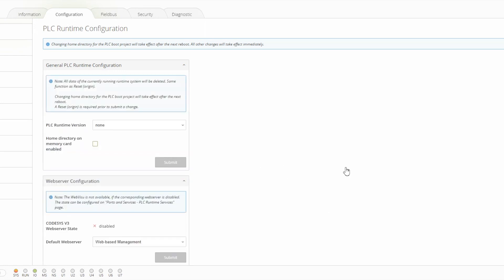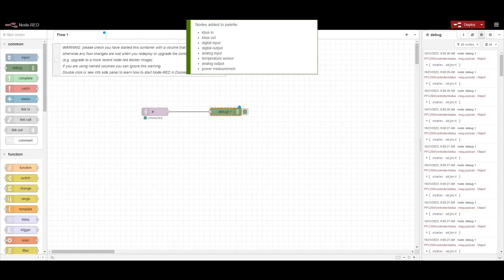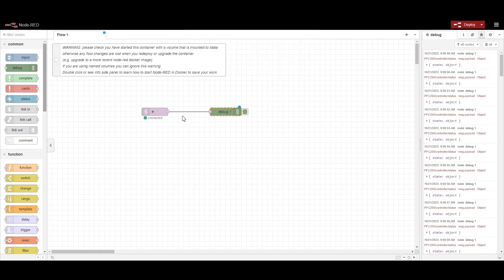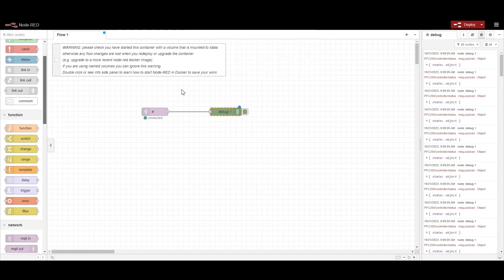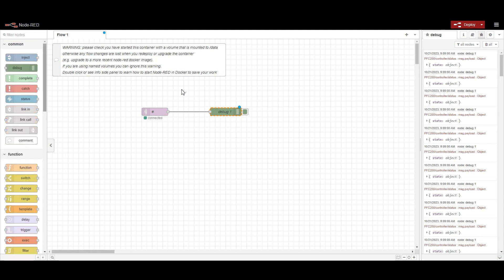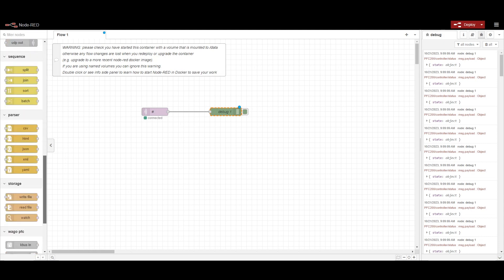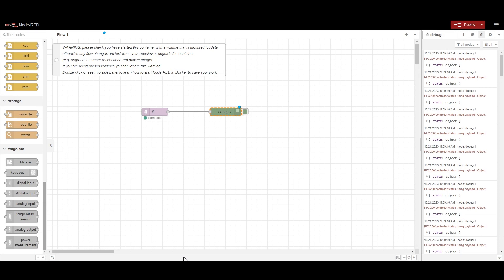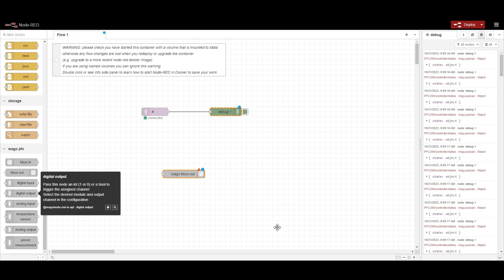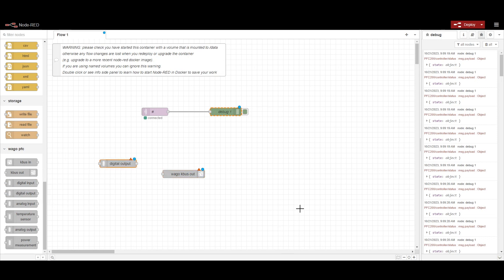We are able to get all the details of the PFC200 — the switch is in run mode and all connected IOs are shown. We can also see this in the debug output. One important thing to check: we have to set the PLC runtime version to 'none' because we are not using CODESYS, so it will directly connect to the I/O. All the nodes are added into the palette and now we can use those nodes to configure the I/O.